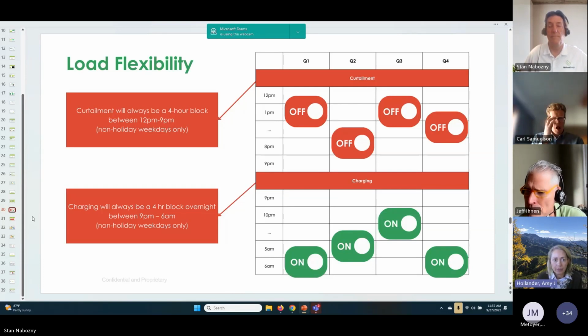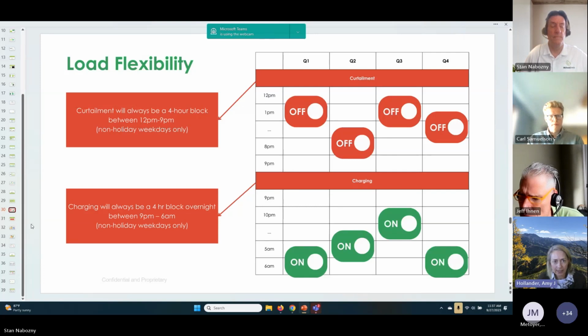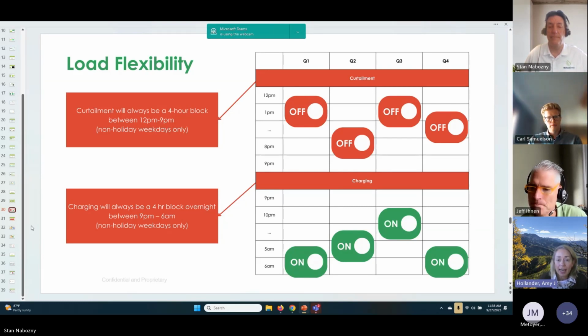So what you've heard from Stan and others is that the essence of thermal storage is you're going to be chilling and then curtailing. If I were doing the slide over, I'd start at the bottom where you're charging. Xcel Energy is only going to require charging over a 4-hour block overnight, and the discharging or curtailment will always be a 4-hour block. That's all the product requires in order for you to get the incentive.